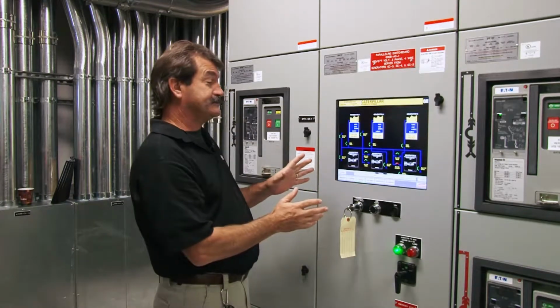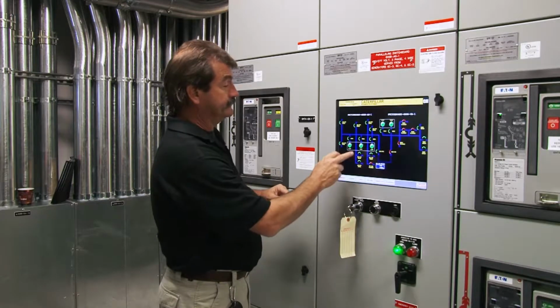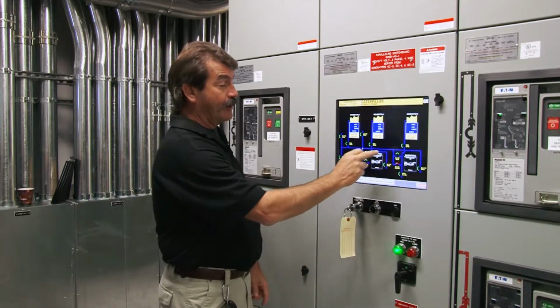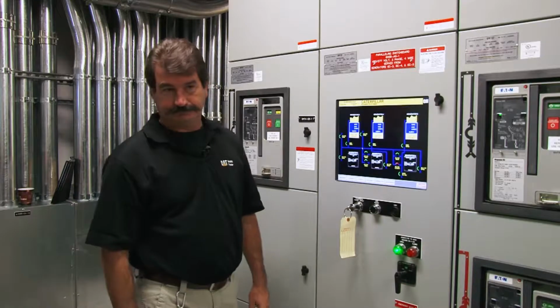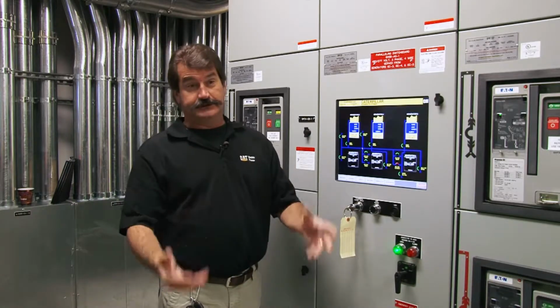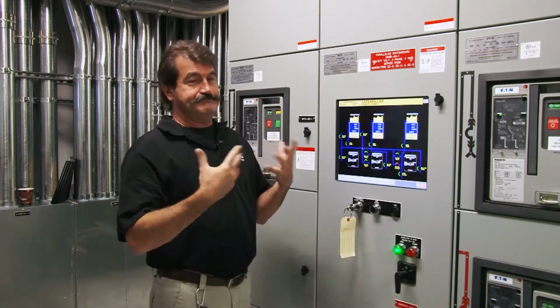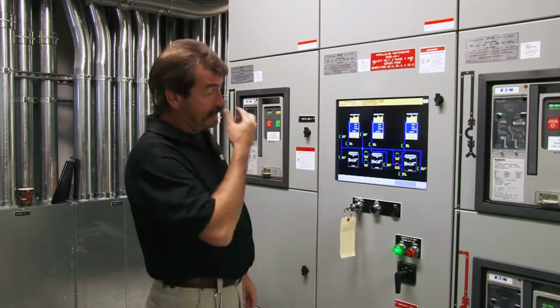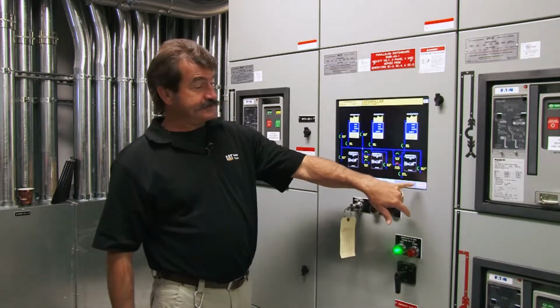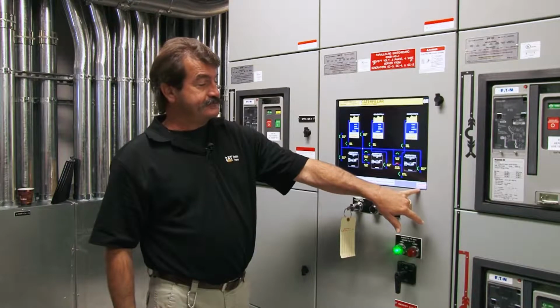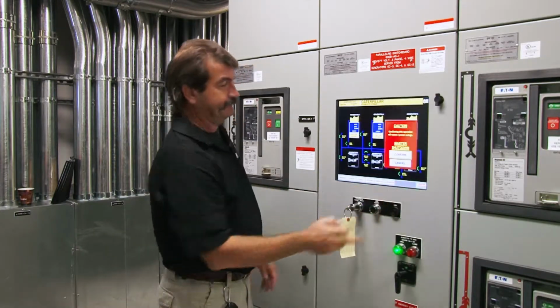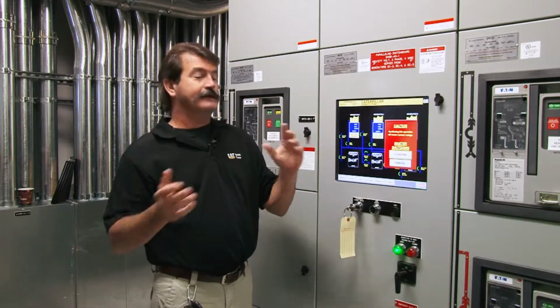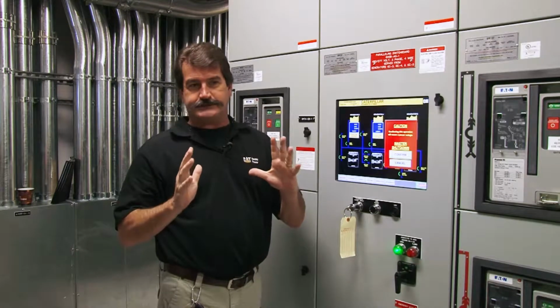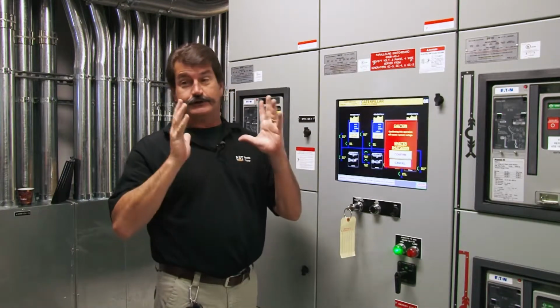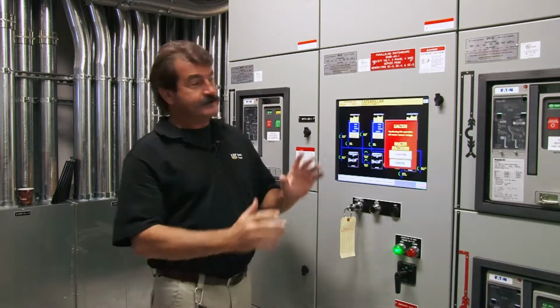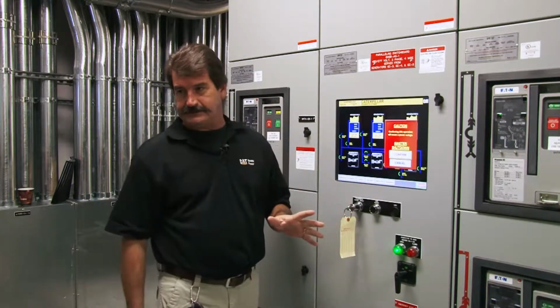With the exception of if you go to off on your gens — that'll let you go to off, but you really have to try for that one. If you want master shutdown, watch: I hit master shutdown, and a confirmation screen pops up asking if you're sure, because it's going to cause a power outage.